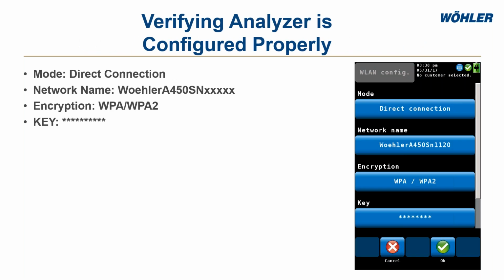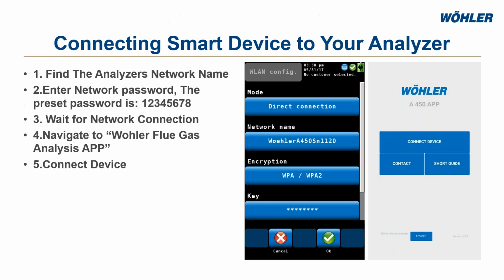So here's how you would essentially connect to the app. Like I said before, as long as these readings are all factory set, your analyzer is ready to go. It should be able to connect to the app with no problem. When you connect to the app, the first thing you want to do is go to your smartphone and go as if you're connecting to a new Wi-Fi signal. The iPhone or Android is going to display a network name that says Wöhler A450 and then gives your serial number. You would click on that, and it's going to ask for a network password. The standard password is 12345678. You type that in, and it's going to establish a connection between the analyzer and phone.